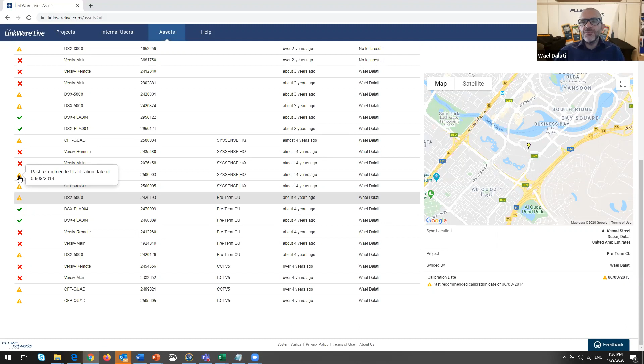You see some green, some orange, and some red. Some people ask me, what is this multicolored setup you have? Well, frankly, this is the CFP quad, the fiber OLTS module that we have. If I hover the mouse over it, it tells me it's past the calibration date of 06/09/2014. So that module is out of calibration.